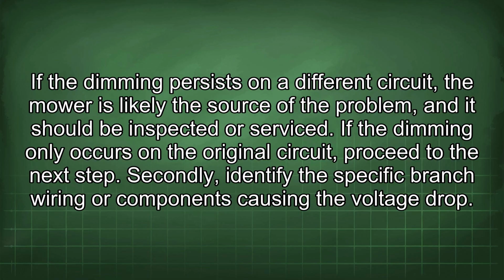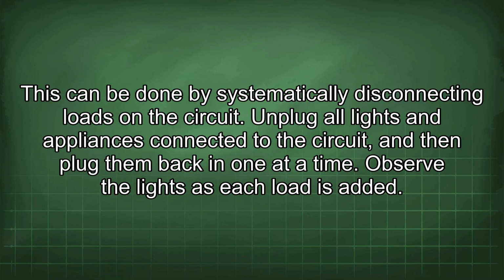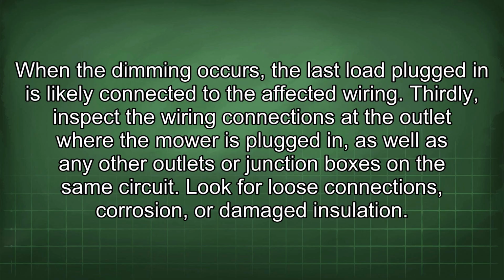Secondly, identify the specific branch wiring or components causing the voltage drop. This can be done by systematically disconnecting loads in the circuit. Unplug all lights and appliances connected to the circuit, and then plug them back in one at a time. Observe the lights as each load is added. When the dimming occurs, the last load plugged in is likely connected to the affected wiring.